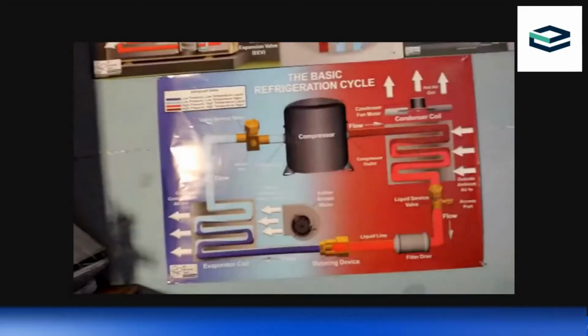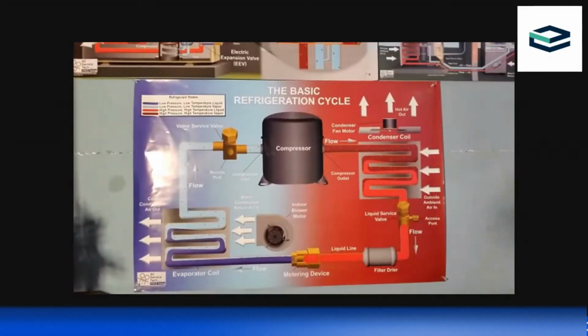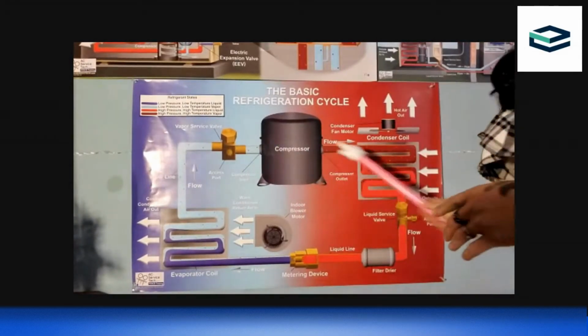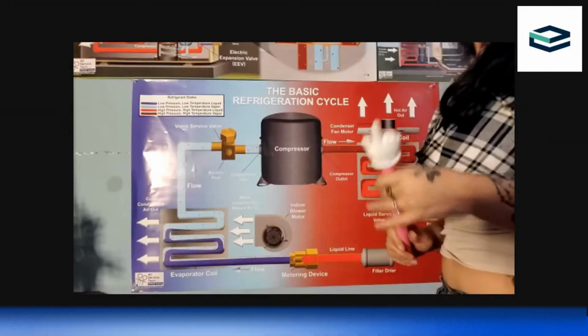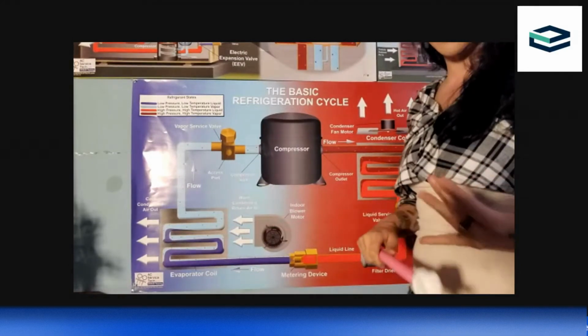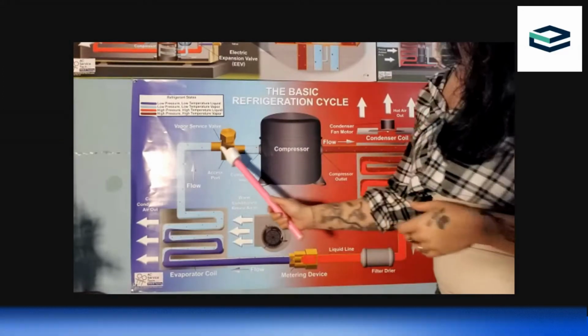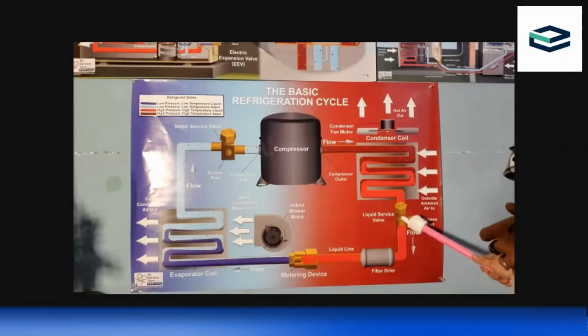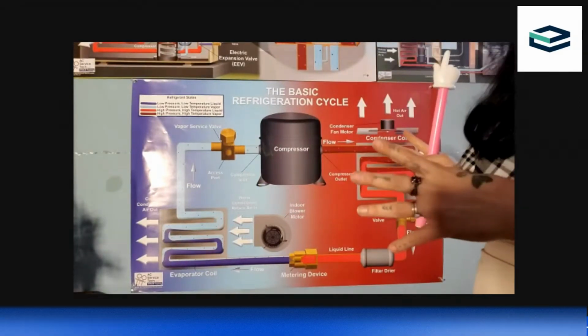So when we finally gauge up, we need to know what we're seeing, right? So I'm going to turn you guys back to the diagram, and I'm going to show you what's happening for each of the things that you'll see on your manifold or on your JobLink app. One of the things that we'll show you is the pressures of each side. Refrigerant goes by pound, and I guess you could measure it by gallon if you wanted to. We use PSI, which is pressure. So pounds of pressure, basically. So when I hook up my gauges to these two service ports, right, I'm going to then see on my manifold or on my app the pressures of the high side and of the low side.